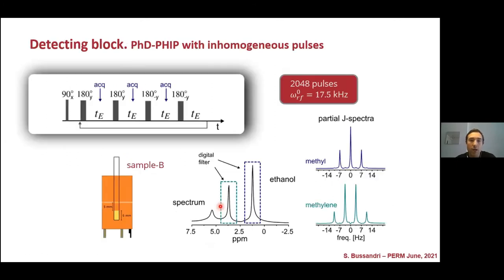Before going to the hyperpolarized sample, we need to test the train of refocusing pulses by itself because we now will apply thousands of inhomogeneous pulses. So we place ethanol in the sample B configuration. We perform two different trains of refocusing pulses with digital filters centered at each of the functional groups of the ethanol, the methyl and methylene. And we obtain this partial spectra free of artifacts in a really good accordance with what we expected.